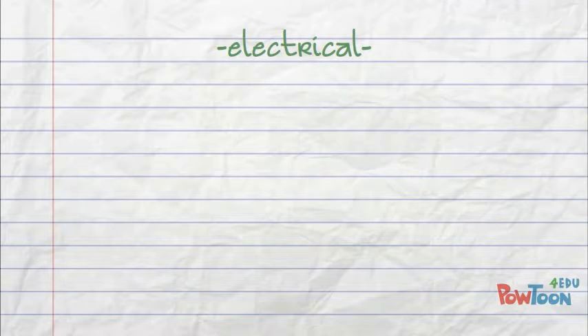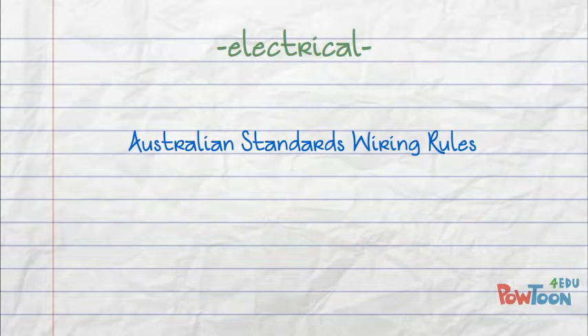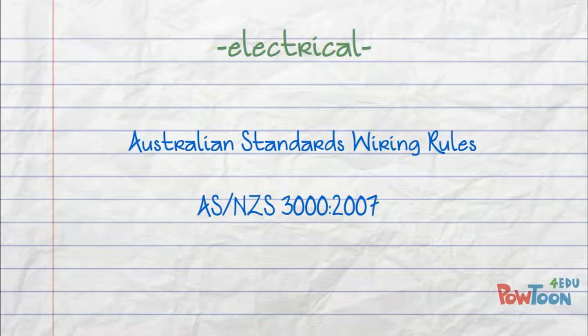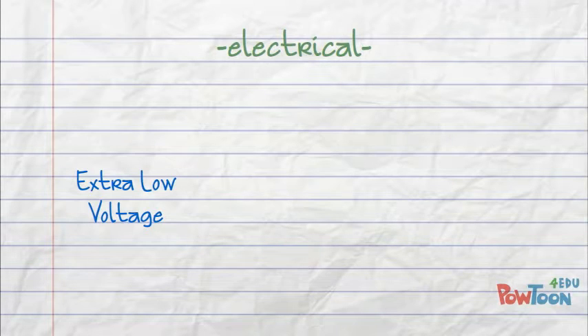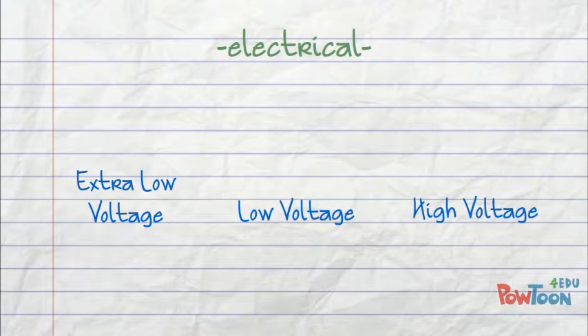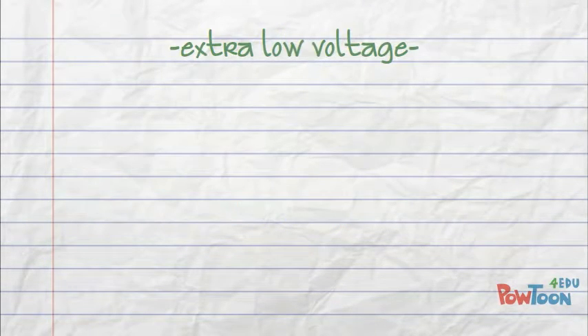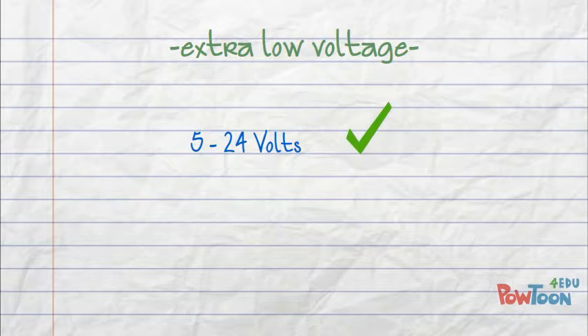Voltage sources employed within a wind turbine generator fall within the three ranges of voltage levels as defined in Australian Standard Wiring Rules AS/NZS 3000:2007. These levels are extra low voltage, low voltage, and high voltage. Extra low voltage values encountered within a wind turbine can range from 5 to 24 volts. For the purposes of definition, the physiological effect of coming into contact with extra low voltage is considered negligible.